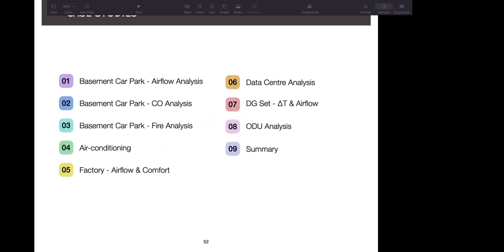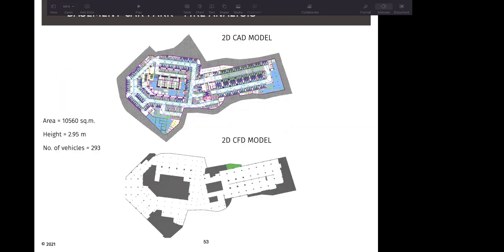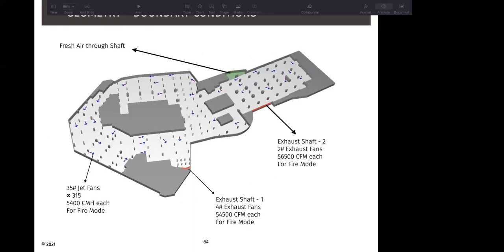Looking at the third example of a basement car park for fire analysis. Again, looking at a 2D CAD model to a 2D CFD model, this basement is about 10,560 square meters. What has been provided is a fresh air shaft marked in green. There are two exhaust shafts. One shaft has two fans of 56,500 CFM, and the other shaft, shaft number 1, has 4 fans of 54,500 CFM. And we have 35 jet fans around the basement to optimize airflow.